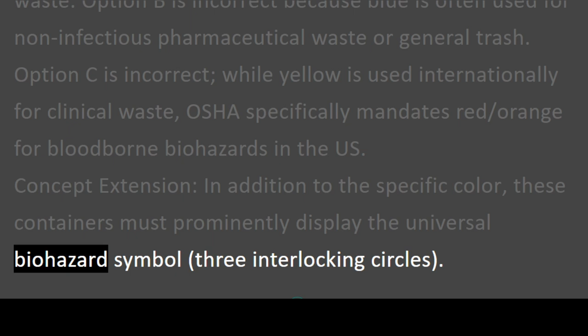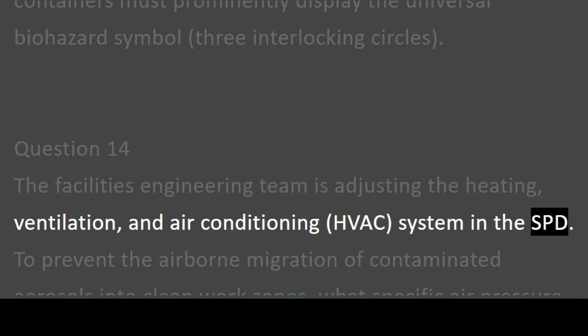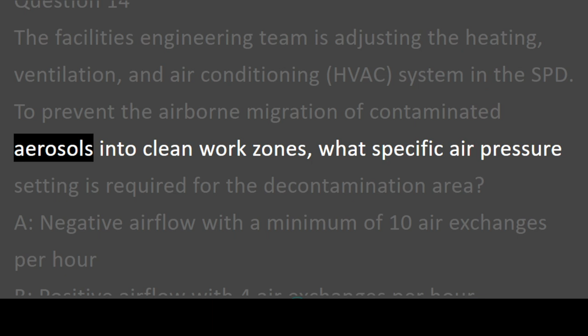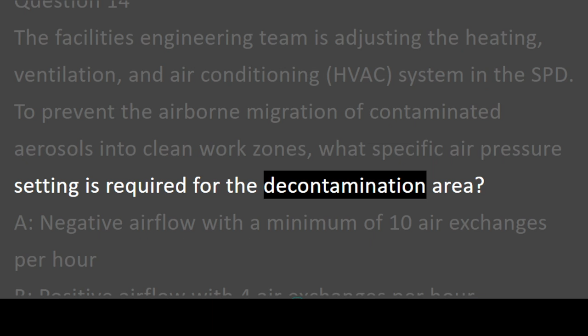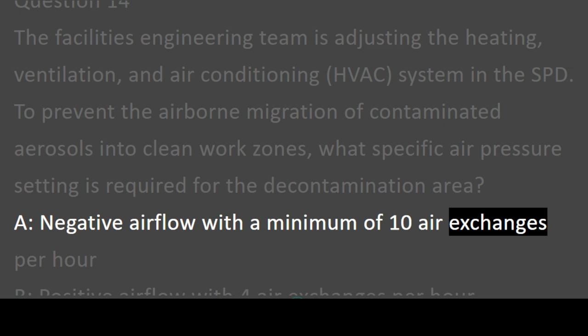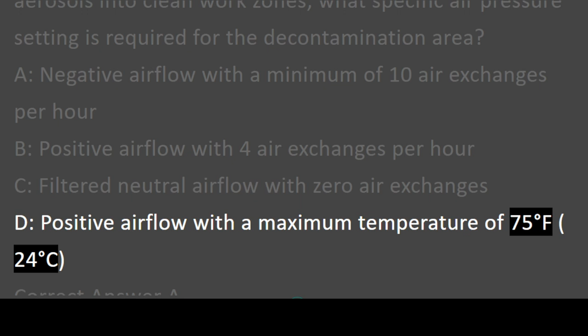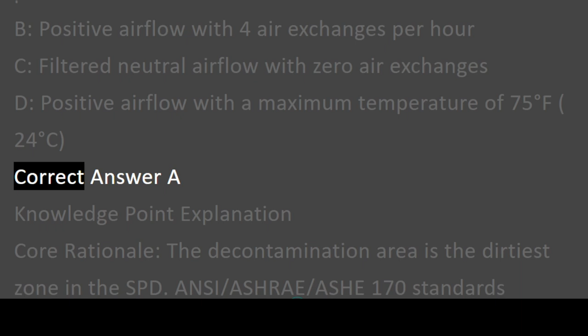Question 14. The facilities engineering team is adjusting the heating, ventilation, and air conditioning (HVAC) system in the SPD. To prevent the airborne migration of contaminated aerosols into clean work zones, what specific air pressure setting is required for the decontamination area? A. Negative airflow with a minimum of 10 air exchanges per hour. B. Positive airflow with 4 air exchanges per hour. C. Filtered neutral airflow with 0 air exchanges. D. Positive airflow with a maximum temperature of 75 degrees Fahrenheit, 24 degrees Celsius.